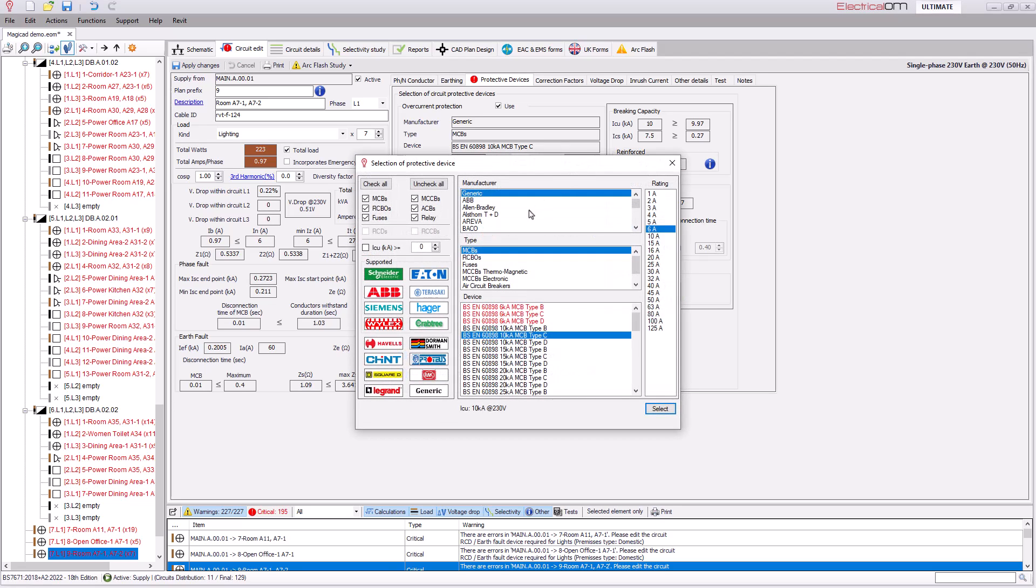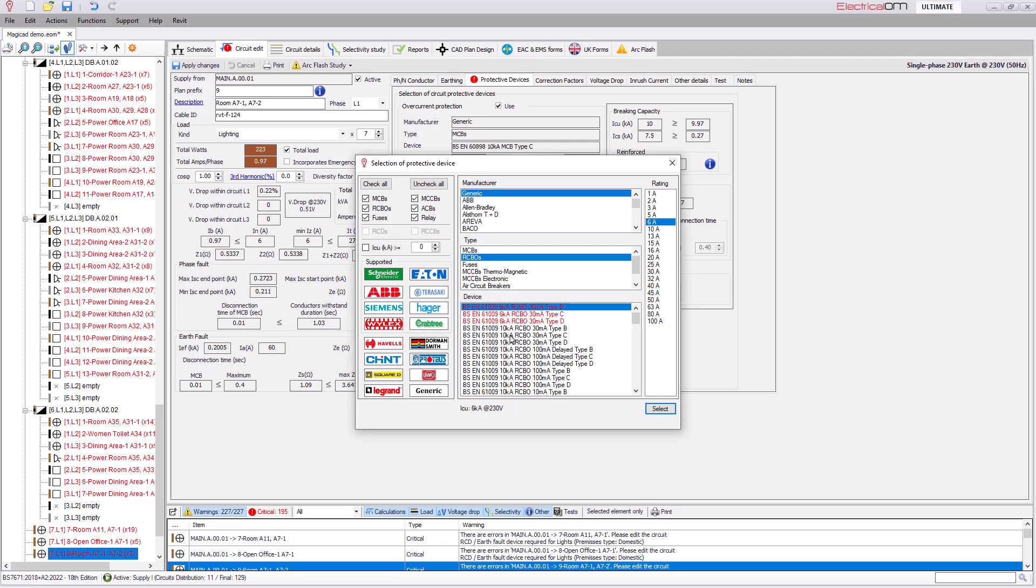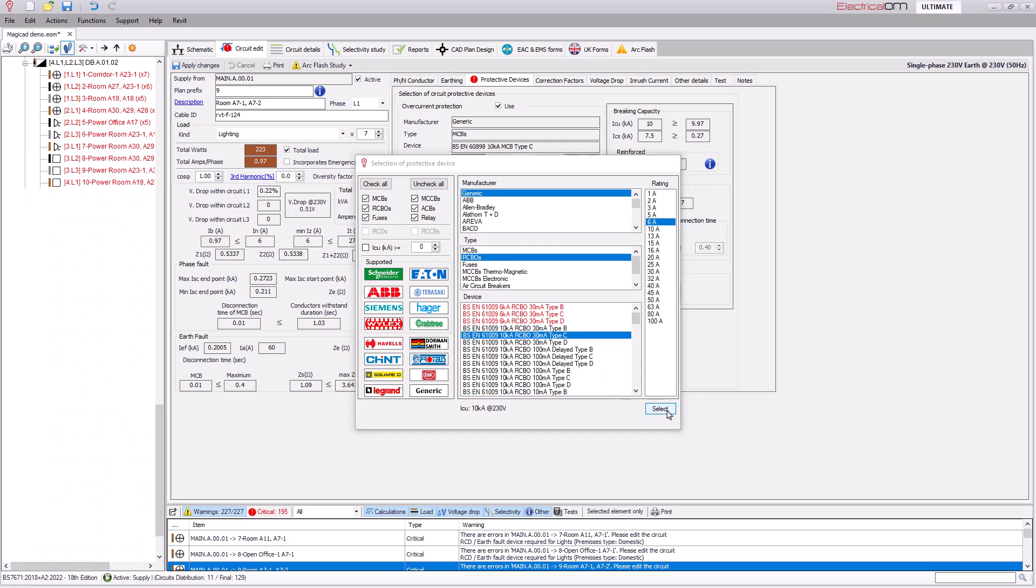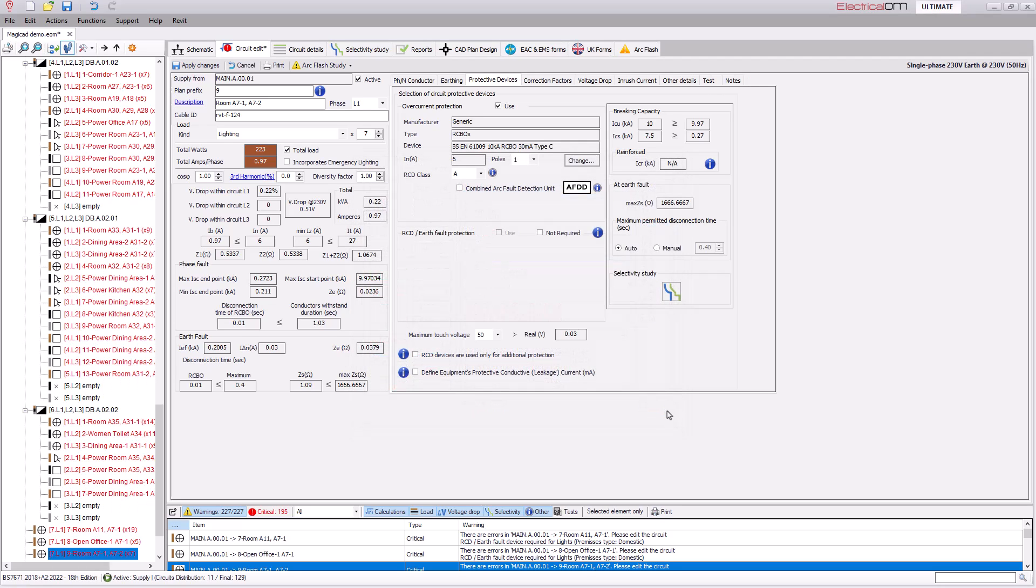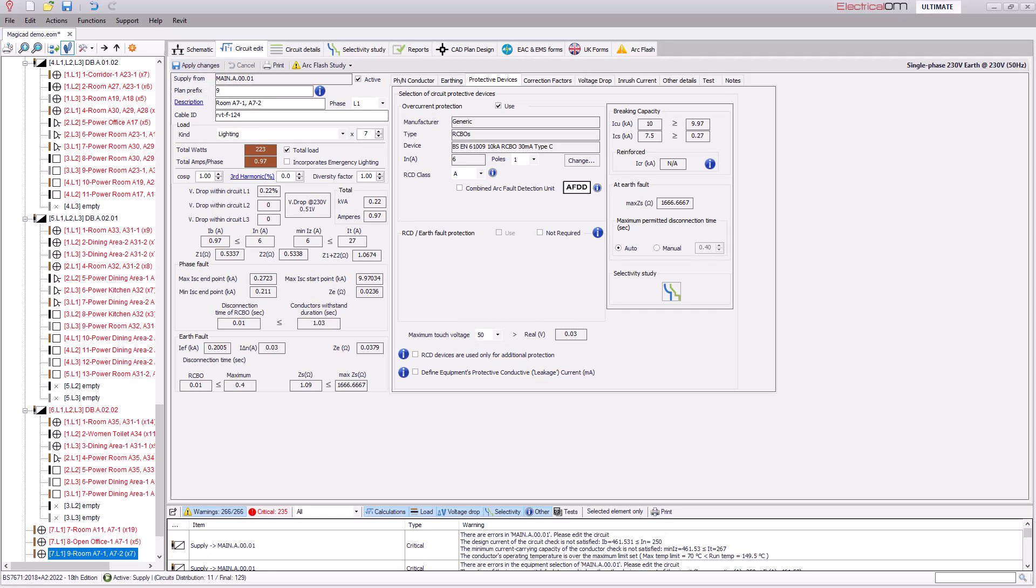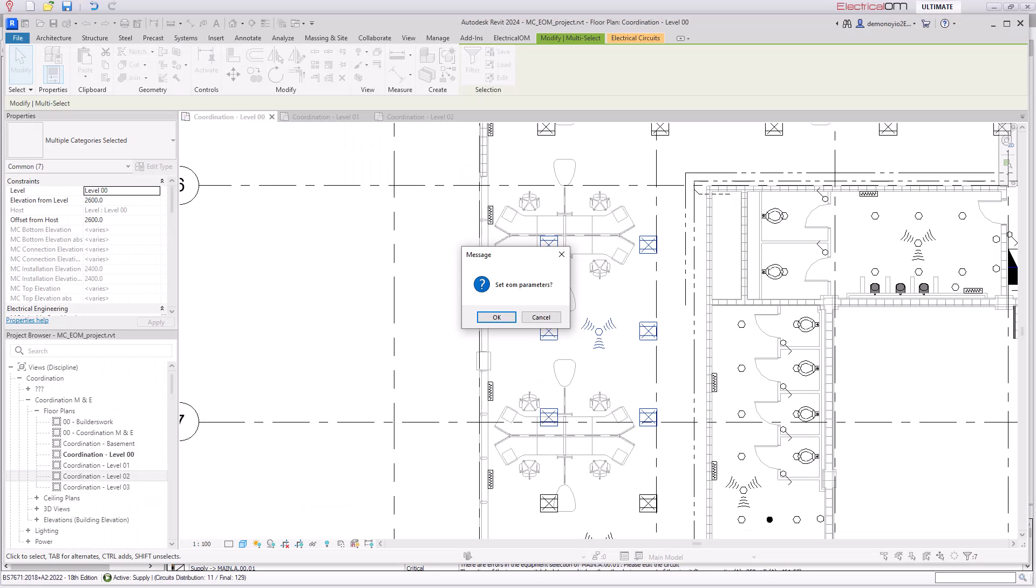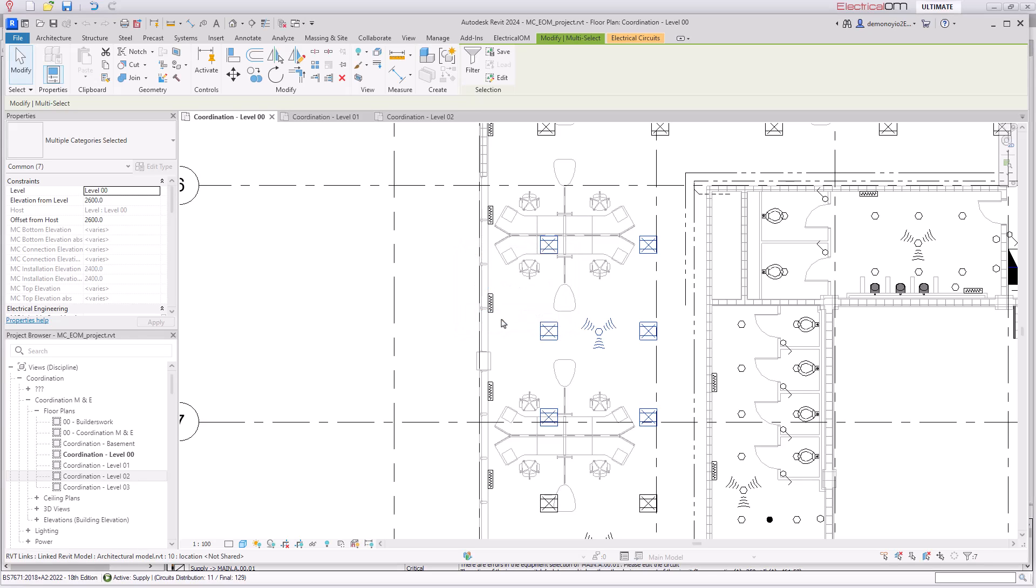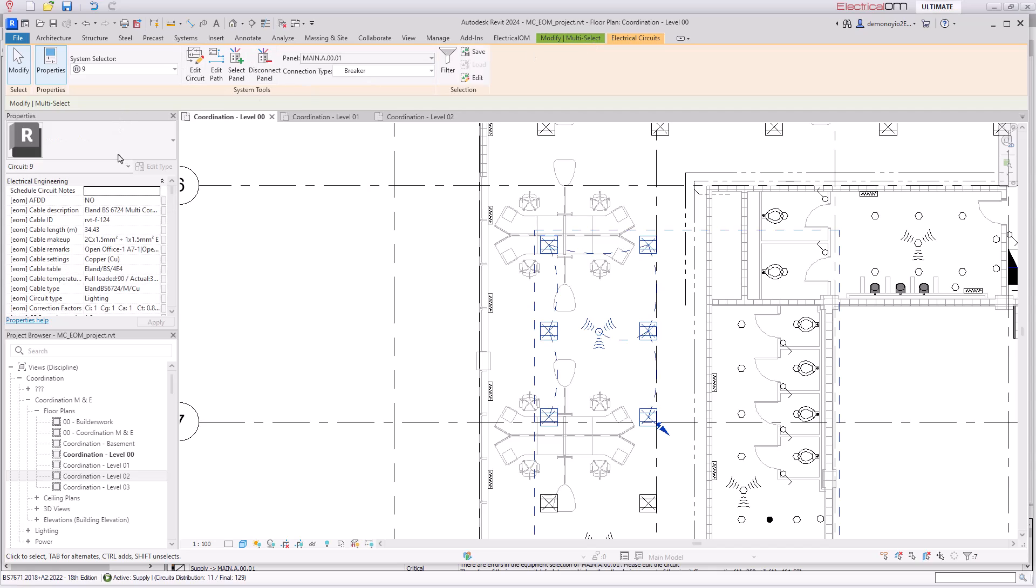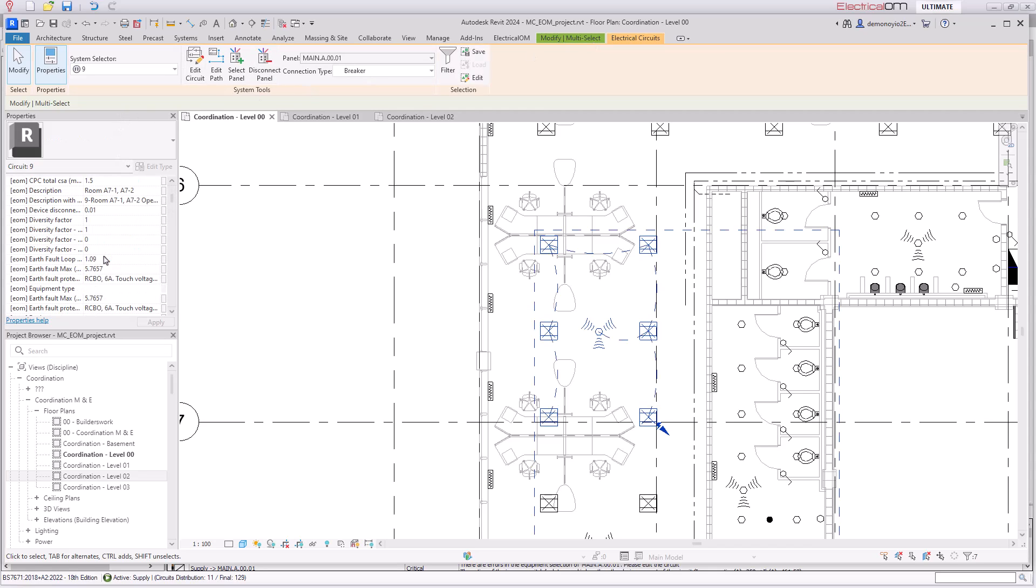By selecting the change option under protective devices this brings up the device database where from here I can select a protective device and in this case it will use a RCBO which is 30mA and a 10kA rating and a C curve. The warning related to the RCD has now been removed and as before as we saw in MagiCAD a modal message will appear with the new parameters to be set as EOM.